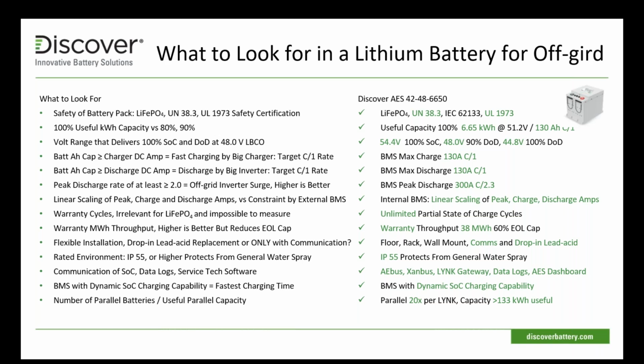Installation options: can you do a drop-in lead acid with the battery, or can you only use communication? Some of the battery systems will not function without a communication system with the inverter charger. Some batteries have no communications out there, and there are advantages and disadvantages to all of that. In our system, you can do it either way. You could drop in lead acid with no communications, or you can set up communications with LYNK. Whatever you like. We also have fairly flexible requirements.